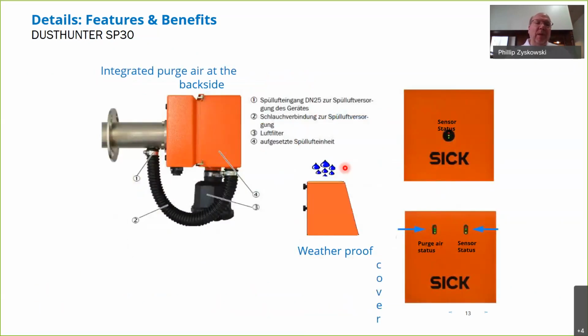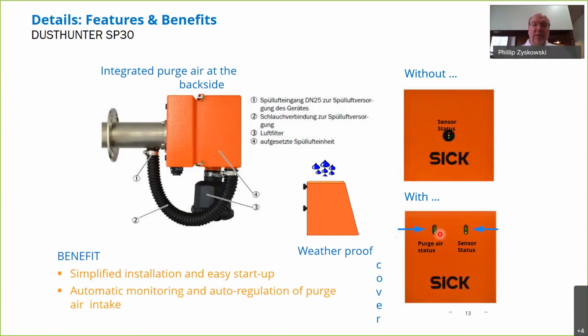I mentioned the available purge. I think it's important for you to understand that that is not required, but again, what's kind of neat is with the purge, you've got a sensor status light on the outside, and then without it, you just get the sensor status. So when you have the purge unit, you also do have a little LED bar indicating the integrity of your purge. So it's a visual indicator. You don't need any other type of control module. So it's very simple to set up. And with the auto regulation of the back purge, it's very low maintenance.